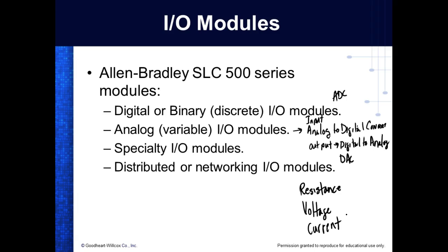Now, why we do that is that if we use voltage, these are going to be low current or high resistance circuits, which makes them more noisy to electromagnetic interference. It's almost impossible for electromagnetic interference to produce a current.